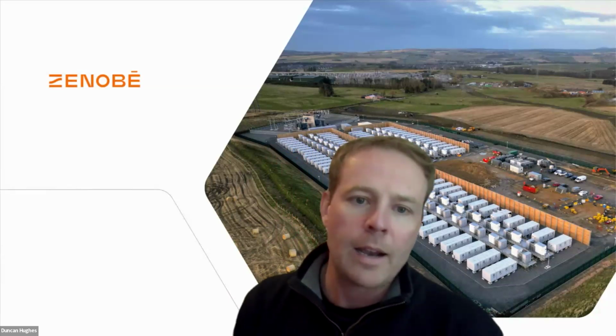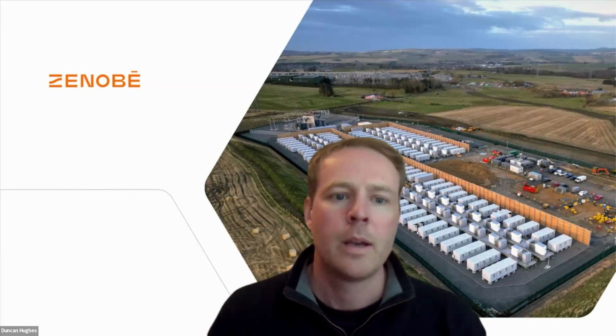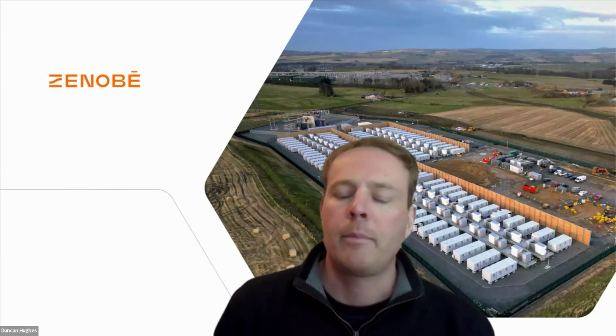The battery at Black Hillock - people often talk about battery projects and it can be hard to visualize, so handily we've got the picture behind us that you can see on screen. For context, it's round about 9 acres, sort of 5 football pitches in size, so pretty big - a proper grid scale, power station sized asset. Our battery site is actually around 1 kilometre away from the SSE transmission substation, so we connect to that substation via an underground 275 kV cable between the two sites.